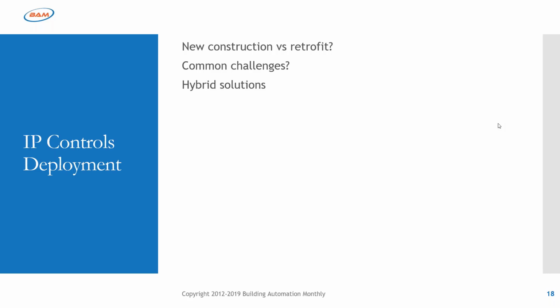Yeah, the bigger issue is that you've got someone on a ladder in the ceiling, or in the mechanical room, and you're not paying any attention that they're in the ceiling messing around with your controllers. I would say you have a physical security issue way before you have a network security issue. With that being said, a lot of these manufacturers do support security at the port level, as well as certificating. So they definitely have that. Talk to your manufacturers and they'll be able to tell you about that.